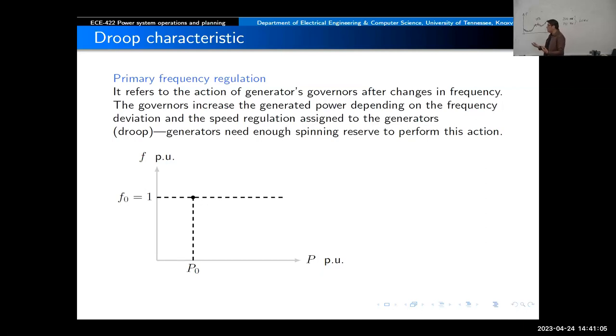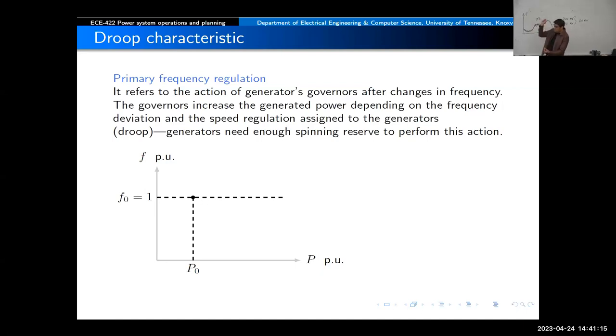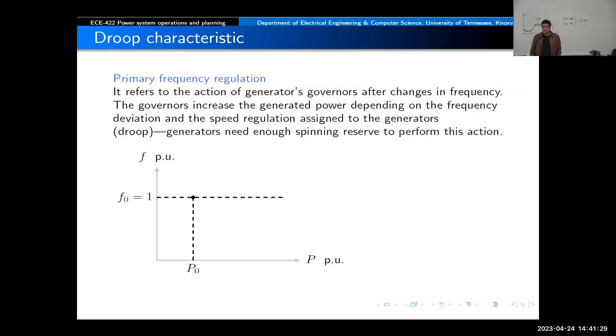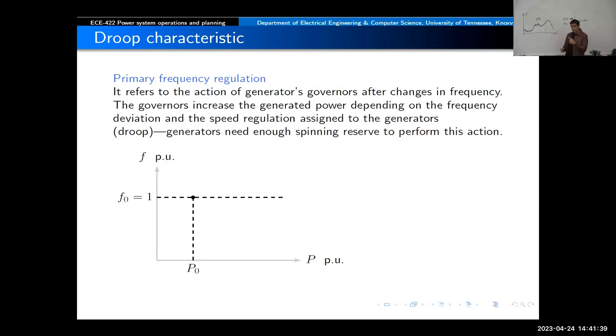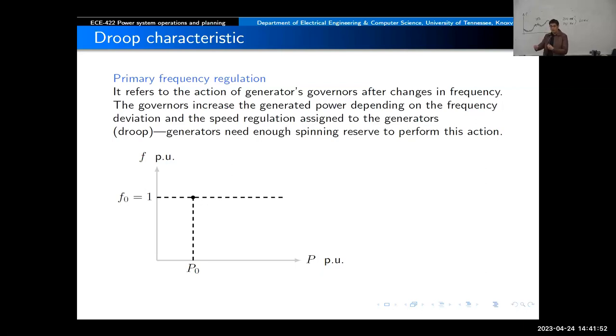When the frequency goes down, what do we need to do to solve that problem? We need to use the spinning reserve, or synchronized reserve as PJM defines it, and we need to decide how the power will be increased from each of the generators that are connected to the system. For example, let's say the frequency goes down to F1 — we need to define that the power from that generator will be P1.